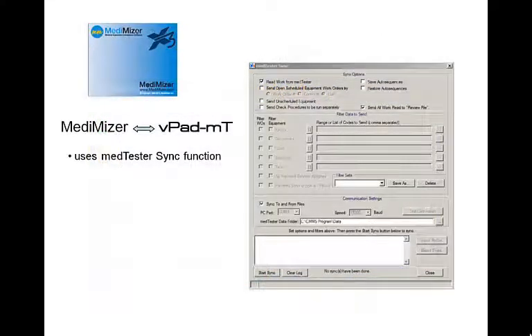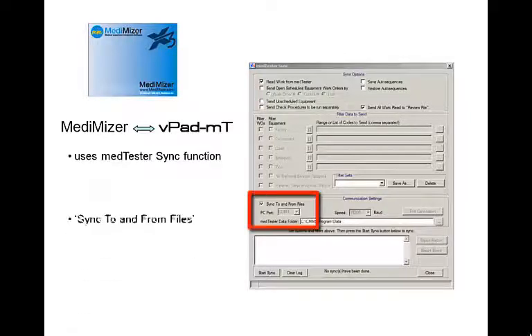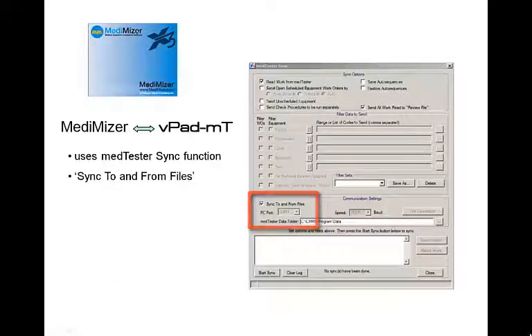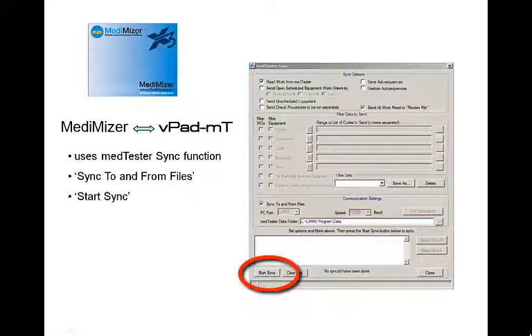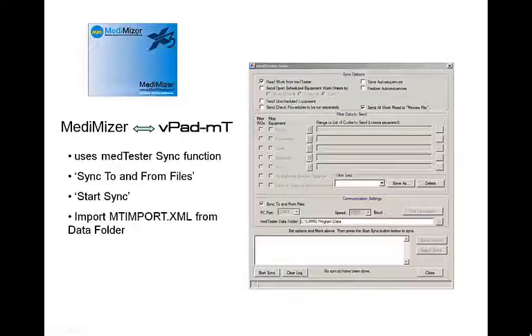In the MediMizer program, once again select the MedTester Sync option and sync to and from files. Move the MT import file to the location identified in the MedTester Data Files field. Press the Start Sync button to import the test report. Because this is a direct file input, importing the test reports takes seconds instead of minutes.